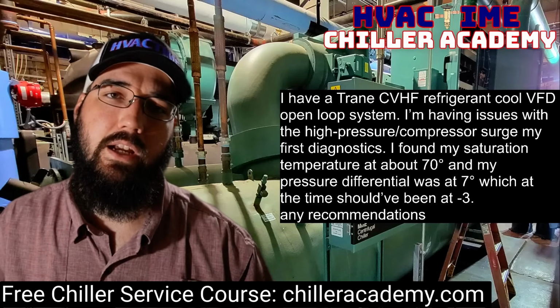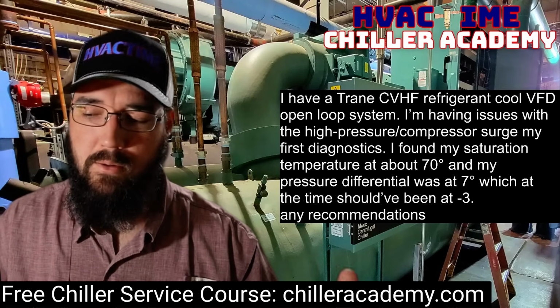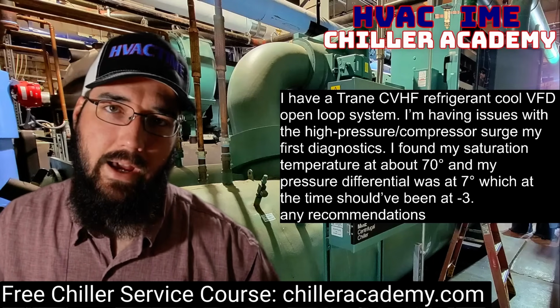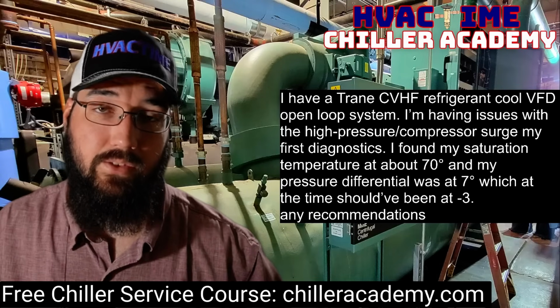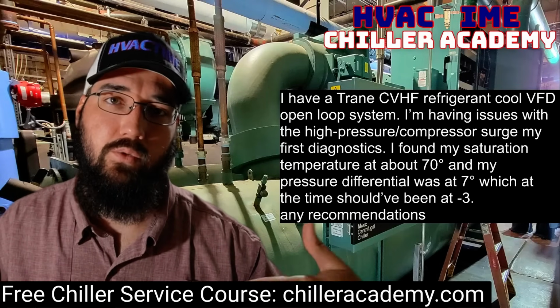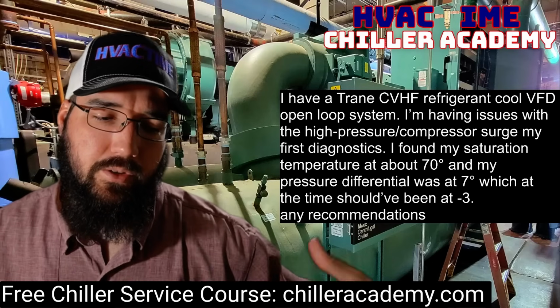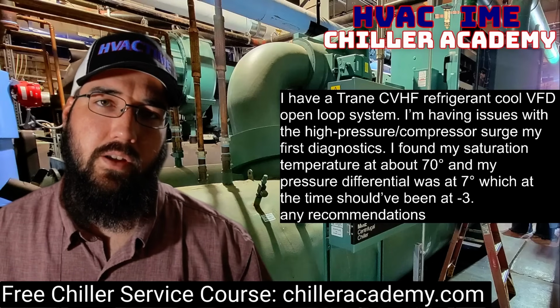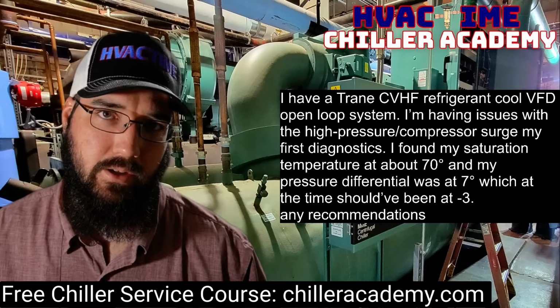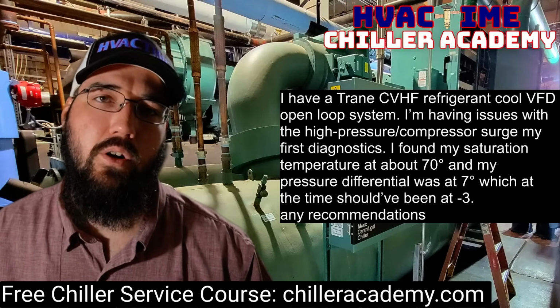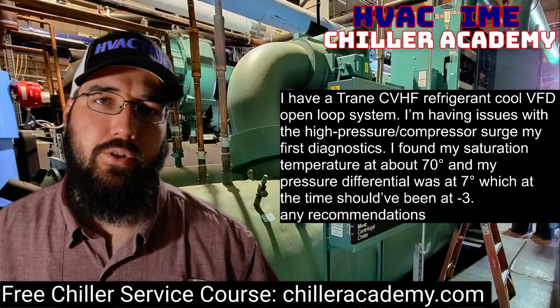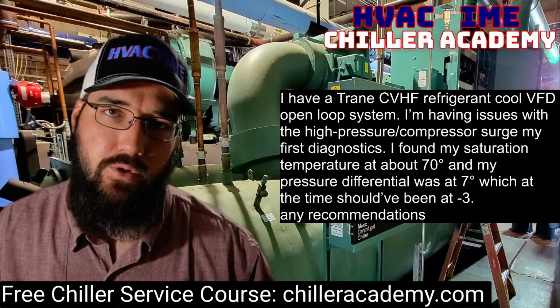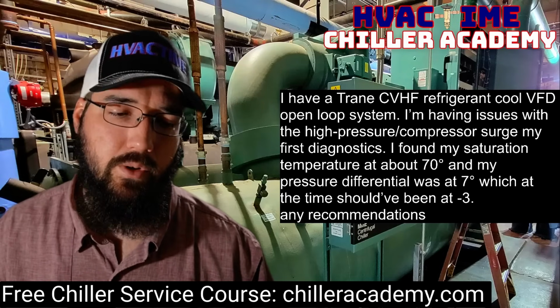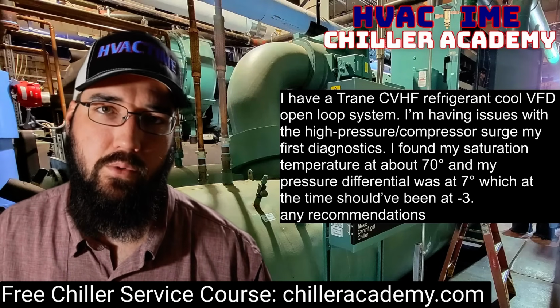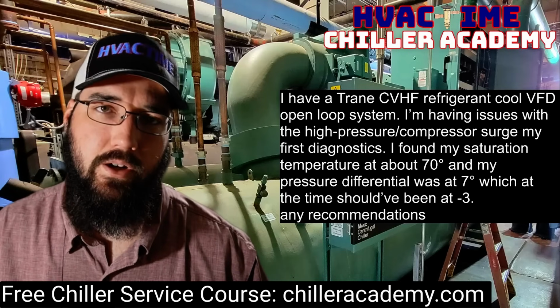Now, I'm really glad that you put one of the RefTech portable purges on it. Those are actually fantastic. And you also put the dryers on it as well. That was another good move. The dryers specifically are going to help with the moisture aspect of it more than anything. If you are having a lot of moisture issues for some reason, which if you're drawing in a lot of atmosphere, that will happen. You will start to accumulate moisture in the system. That's why these dryers need to be there.